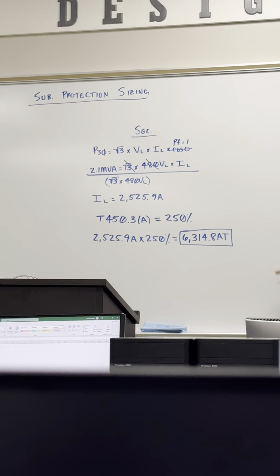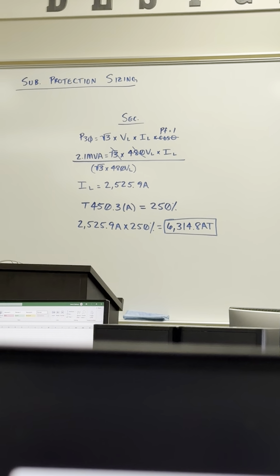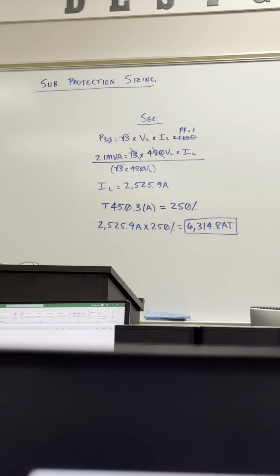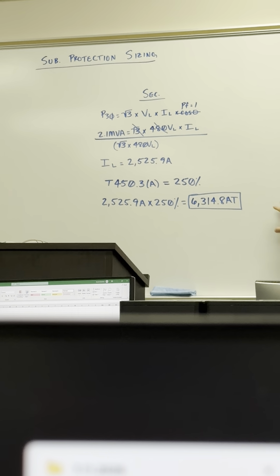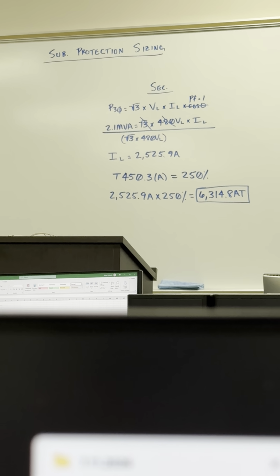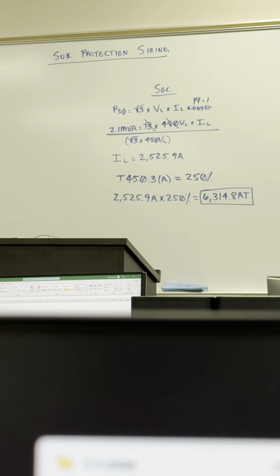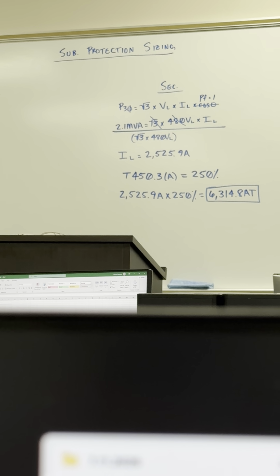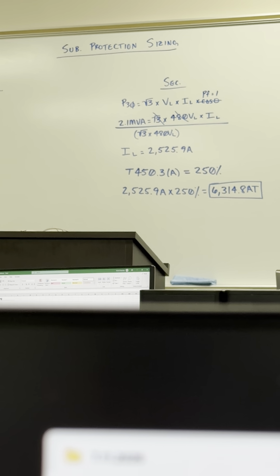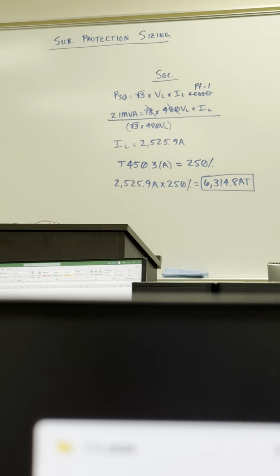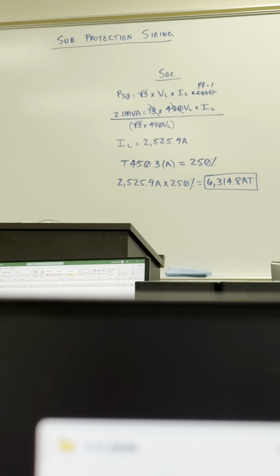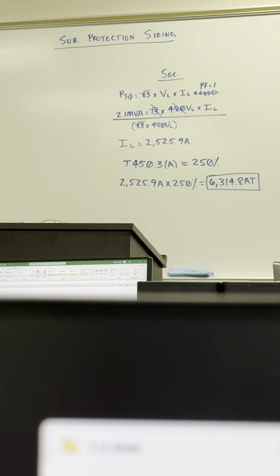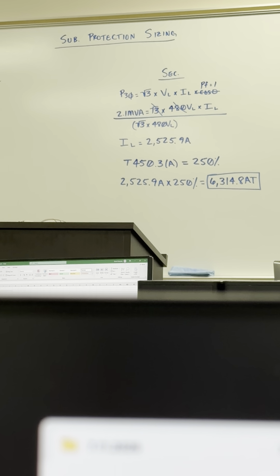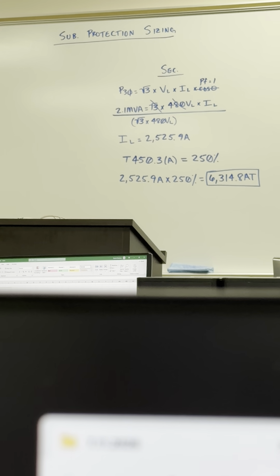So, if you're wondering or noticed that after that calculation, I went ahead and wrote AT and boxed my answer and wrote it up there on the front. So, we're not going to look at table 240.6 this week. Reason being is because these breakers that we're calculating are not fixed trip breakers. So what that means is, it's like if a breaker goes out in your panel at the house and you go over to Home Depot, you can go buy a 20 amp breaker, for example, right? Well, that 20 amp breaker, that's all it'll ever be, a 20 amp breaker. You can't go in there, you can't modify how much amperage it can handle. I mean, you could, but legally, in terms of the code and what the manufacturer produced, you cannot do that with that kind of breaker.